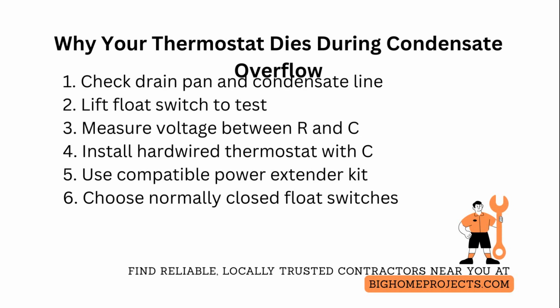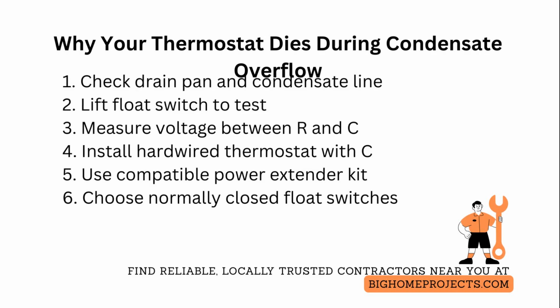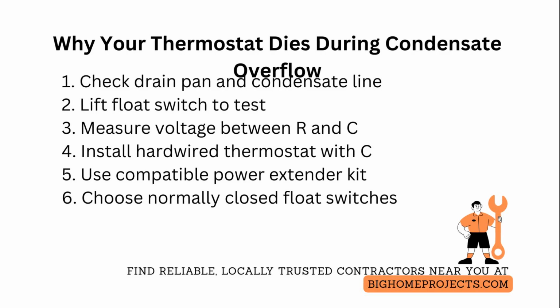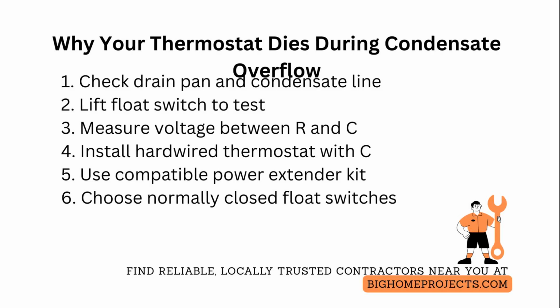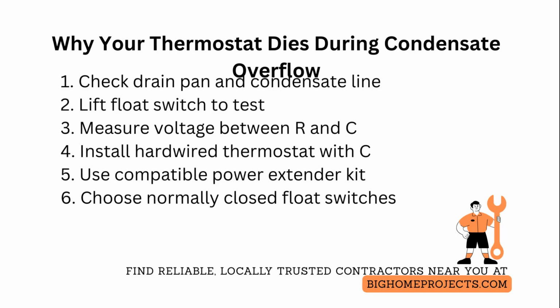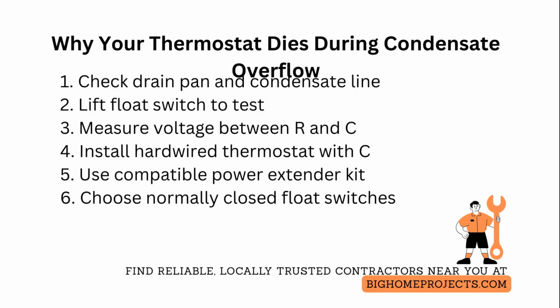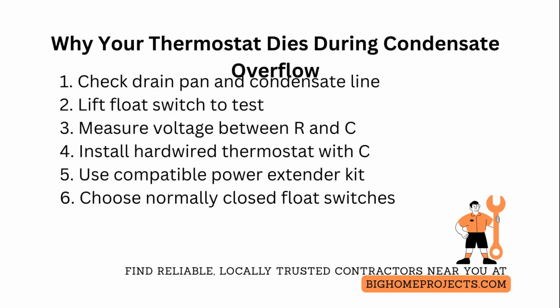Fifth, when replacing float switches, choose normally closed float switches that open only on overflow so the control wiring behaves predictably. Avoid adding relays without understanding whether you need isolation between low voltage and safety circuit. Sixth, document every wire at both the furnace and thermostat, label them, and photograph before disconnecting so you can restore correct connections. Seventh, when in doubt, add an isolation relay powered by the furnace 24-volt transformer so the float switch only interrupts the relay coil and not the thermostat supply, keeping the thermostat lit while still protecting the equipment.